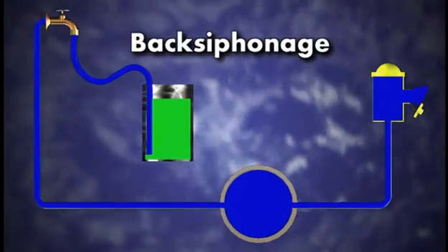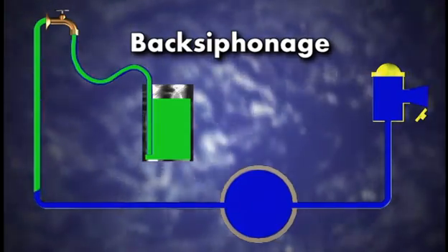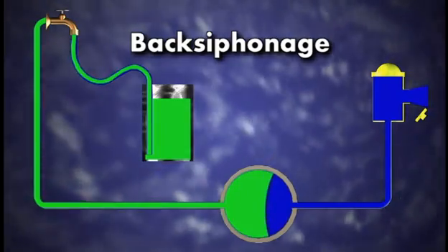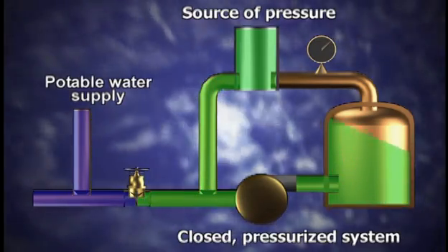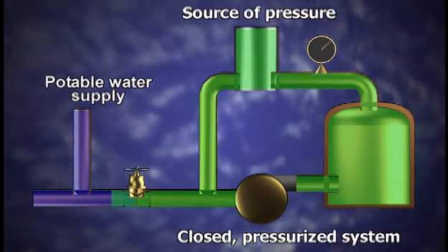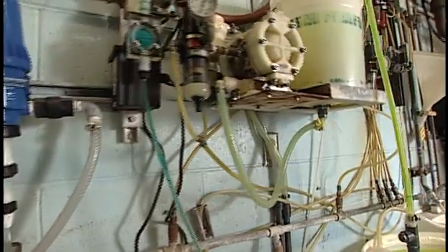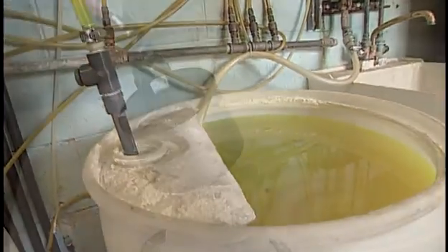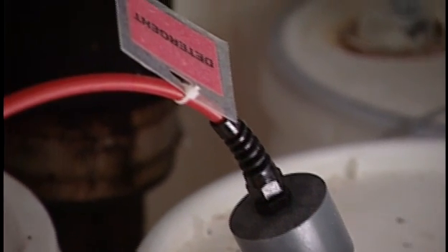Back siphonage is caused by negative or reduced pressure in a water system and occurs during low-pressure events such as a line leak. Back pressure is caused when a potable water system is connected to a non-potable supply operating under higher pressure that pushes contaminated liquid back into the public water system, meaning non-drinkable water or other fluids can accidentally get into your drinking water system when a pressure difference forces unwanted liquids into clean drinking water lines.